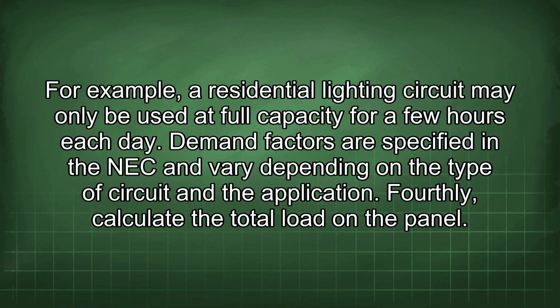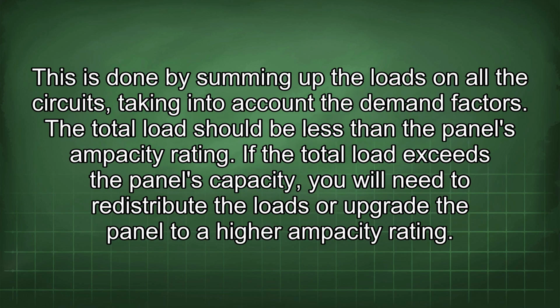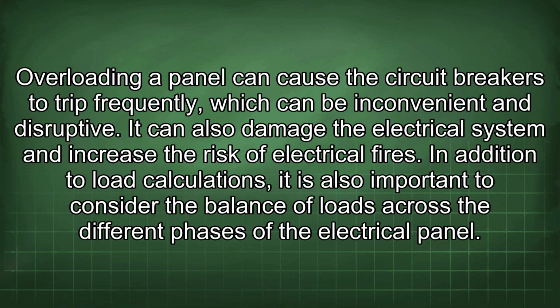Fourthly, calculate the total load on the panel. This is done by summing up the loads on all the circuits, taking into account the demand factors. The total load should be less than the panel's ampacity rating. If the total load exceeds the panel's capacity, you will need to redistribute the loads or upgrade the panel to a higher ampacity rating. Overloading a panel can cause the circuit breakers to trip frequently, which can be inconvenient and disruptive. It can also damage the electrical system and increase the risk of electrical fires.